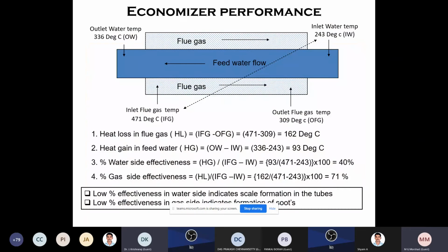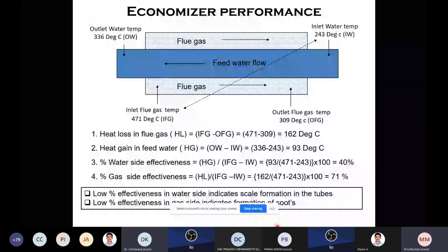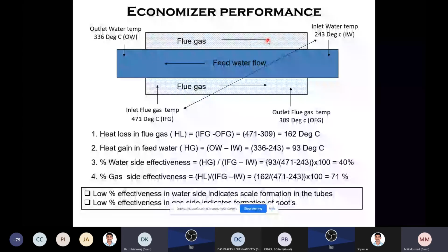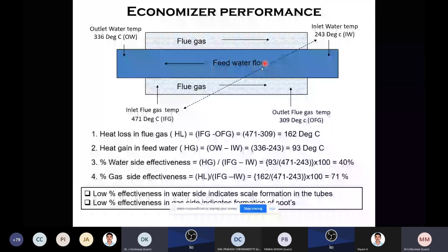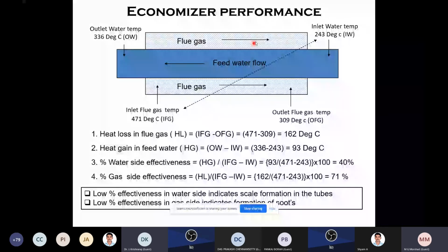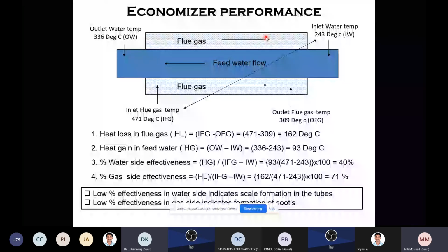Now, economizer performance. Normally, for this type of equipment, we check the effectiveness, how effectively heat is being carried out. So in the economizer, what is happening? The hot flue gas is going out from the boiler and feed water is going to the boiler. Heat exchange is taking place and the feed water is heated by the heat loss. So the flue gas will lose heat, and at the same time the feed water will heat up.